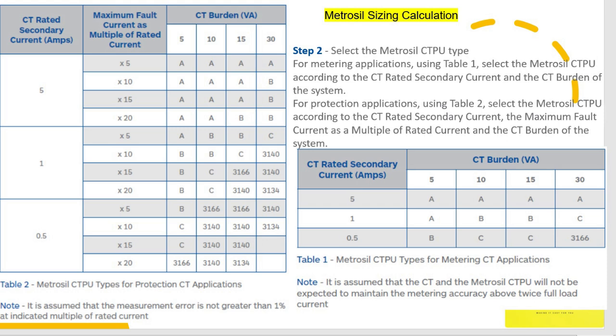For metering applications, using Table 1, select the Metrosil CTPU according to the CT-rated secondary current and the CT burden of the system. For protection applications, using Table 2, select the Metrosil CTPU according to the CT-rated secondary current, the maximum fault current as a multiple of rated current, and the CT burden of the system.